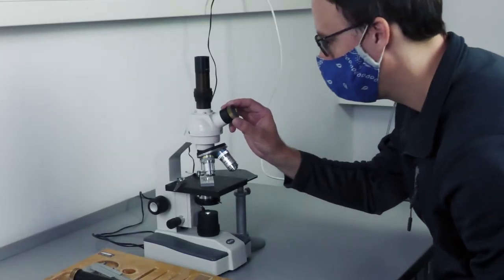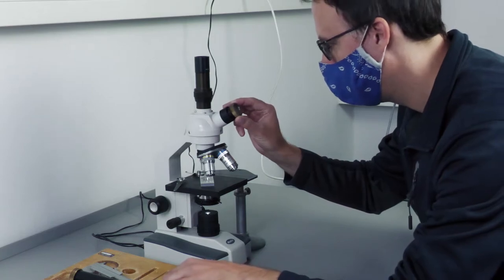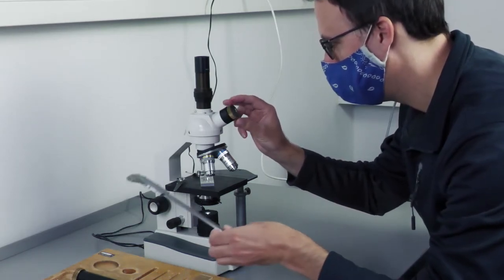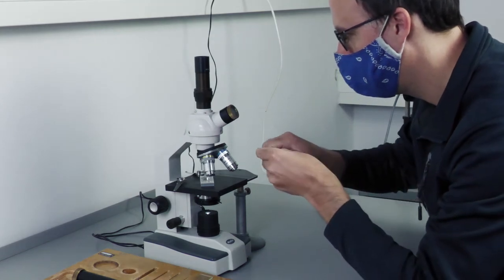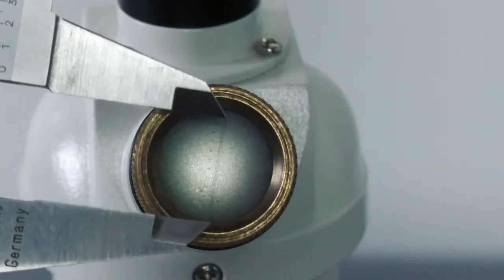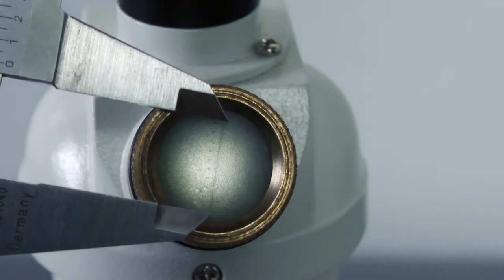Use the inclined eyepiece with a short sliding tube with ground glass. By moving the focusing screen you can focus the real intermediate image of the objective. Please do not turn the objective wheel. Use the calipers to measure the objective image to the corresponding objective eyepiece combination.